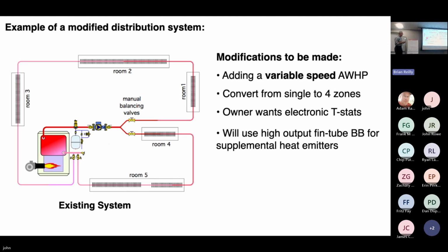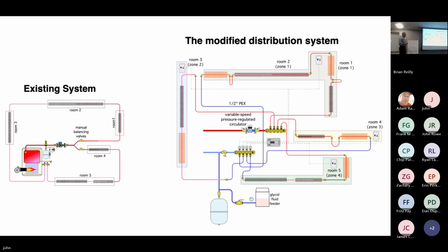Okay. We'll use high output fin tube baseboard for supplemental emitters. Let's say we've made a decision based on water temperature and COP that we need to add some supplemental heat emitters to the system, okay? So here's what we're gonna do. Here's our original system. This is the surgery, after the surgery. What we've done is we've made cuts in certain spots in the copper piping where we can access the copper piping. So, for example, this is still the original baseboard with the copper tube in it. The orange would represent the supplemental emitter that we decided to add, okay?